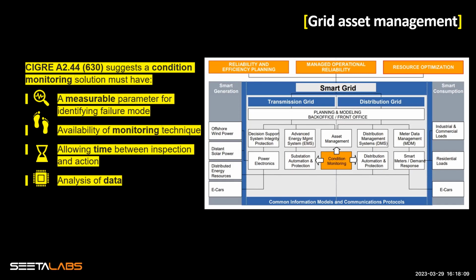When doing that, there is a very interesting parameter: water vapor pressure inside the insulation paper matrix. There is no non-invasive technique with which you can monitor this inside an operating transformer, making moisture monitoring one of the most critical and challenging parts of condition monitoring in transformers. This is just an example.